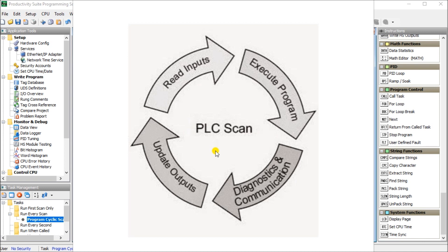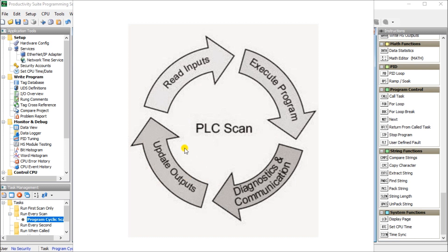Understanding how the program scan will help us in programming and troubleshooting the PLC. The simplest scan cycle of a PLC consists of four steps: read inputs, execute program, diagnostic communications, and update outputs. This continuously cycles through. That's why we call it a cyclic scan.